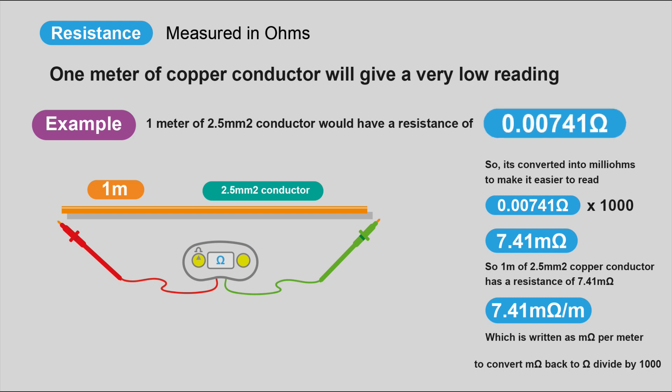That's quite a long number to write down, so we get rid of the noughts. We convert it into milli-ohms to make it easier to read. So we times that number by 1,000 and we get 7.41 milli-ohms. So one meter of 2.5 millimeters squared copper conductor has a resistance of 7.41 milli-ohms per meter.